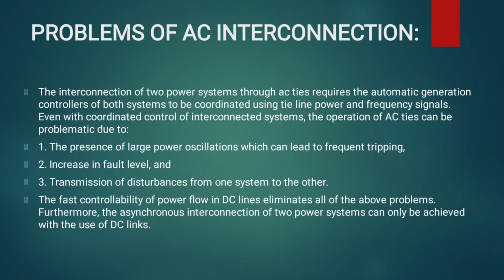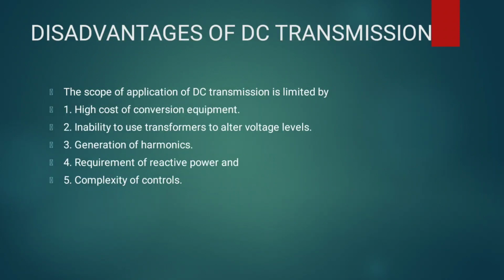The interconnection of two power systems through AC ties requires the automatic generation controllers of both systems to be coordinated using tie line power and frequency signals. The presence of large power oscillations leads to frequent tripping, increase in fault level, and transmission of disturbances from one system to the other. The fast controllability of power flow in a DC line eliminates all the above problems. The asynchronous interconnection of two power systems can only be achieved with the use of DC links.